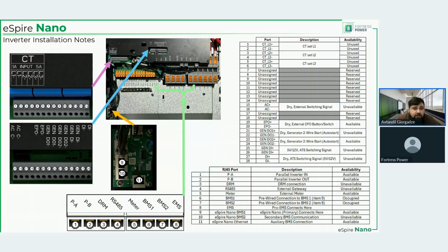Now let's talk about the RJ45 ports. PA and PB, that is parallel A, parallel B. So parallel in is PA, parallel out is PB. That is for the inverters working in parallel. So, for example, if you have 3 inverters, right? PA from the first inverter goes to PB of the second inverter, and PA of the second inverter goes to PB of the third inverter. So that's kind of how you daisy chain these inverters. DRM connection, we're not allowing that.